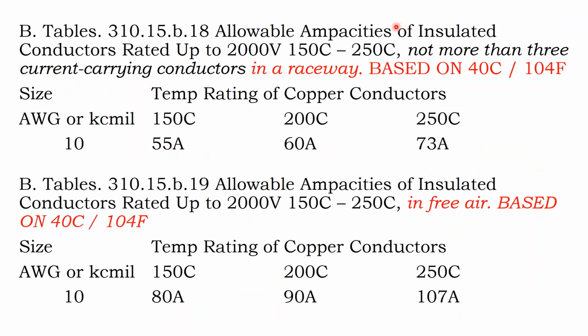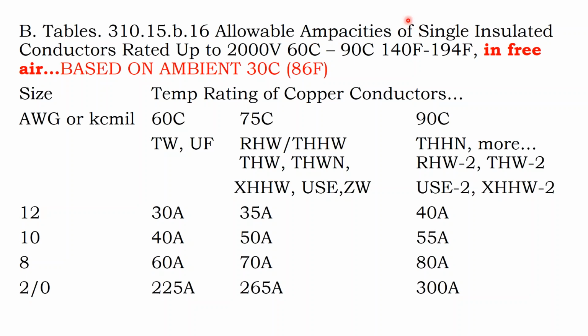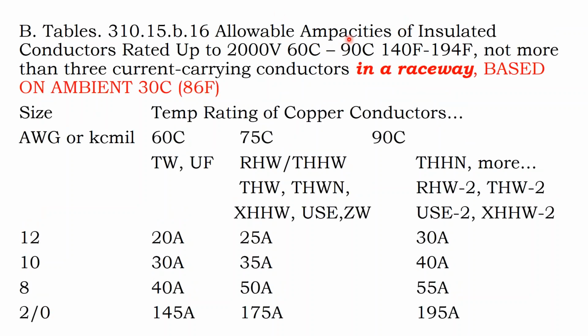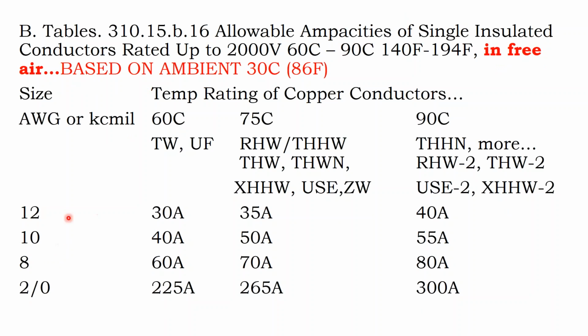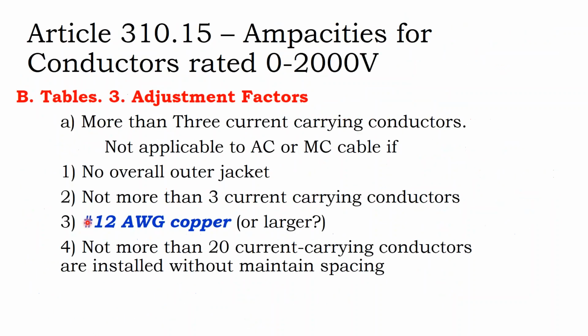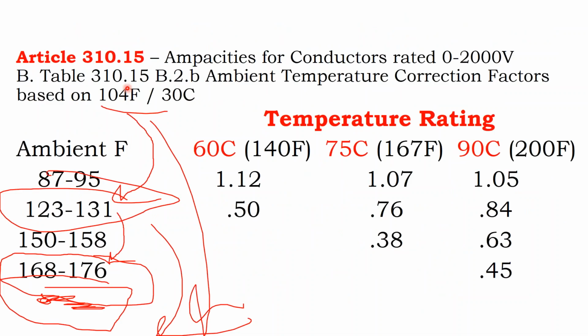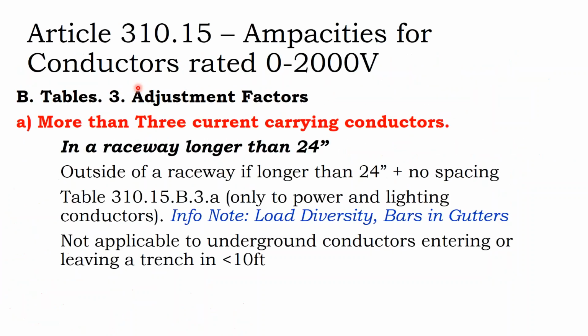So when you see these tables and in the description, it's like this is 86 degrees, but then you have to go and apply temperature correction factors. Here we're seeing it's a 104 degree table, but then it's asking us to pick out our actual ambient. This 104 degrees is just for matching up with table 310.15 B2B.